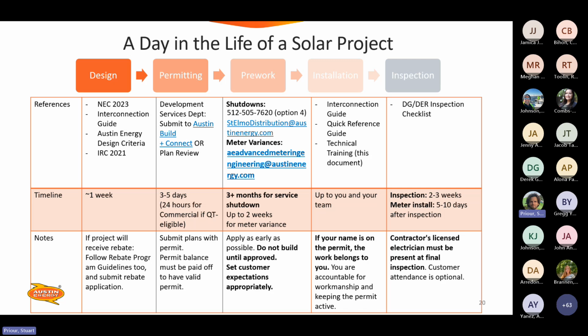And finally, the inspection. We've got an inspection checklist, which is also published in the DIG. Right now we're at a 2 to 3 week wait time, and then 5 to 10 business days after inspection is when the actual meter will be set and the customer will have their final permission to operate. Keep in mind too, the contractor's licensed electrician must be present at the final inspection. Customer attendance is optional. That's your master, your journeyman, or your residential wireman, and they're there so that they can open up equipment and test functionality of the system for us.